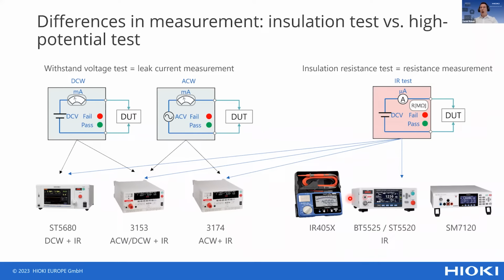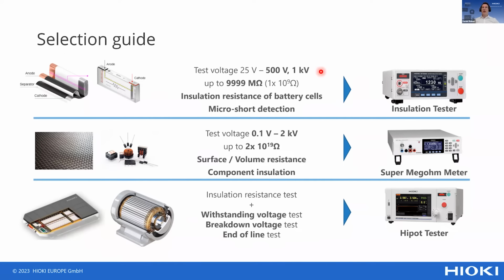And the reason how to choose is basically shown here, depending on the level of voltage being applied. So we have the latest product, BT5525, which is applying 500 volt, specifically looking at the battery industry, so on cell level. While the ST5520, more general purpose insulation tester, is capable up to 1 kilovolt. Also, we have the other models, which have a higher test voltage, but the differentiation between those 2 is basically the resistance value. While with 10 gigaohm, you would be absolutely fine when testing battery cells. The component testing requires a much higher resistance value, and therefore the display range of resistance value is much higher.